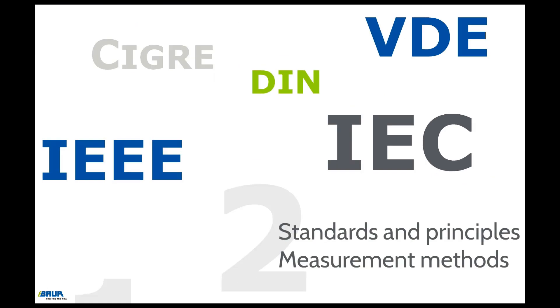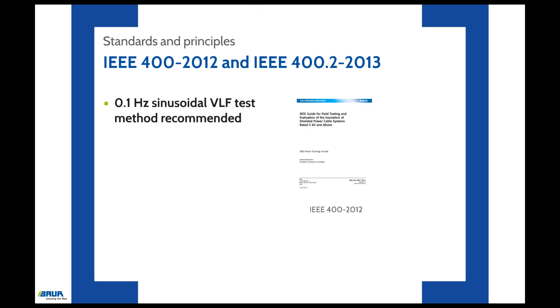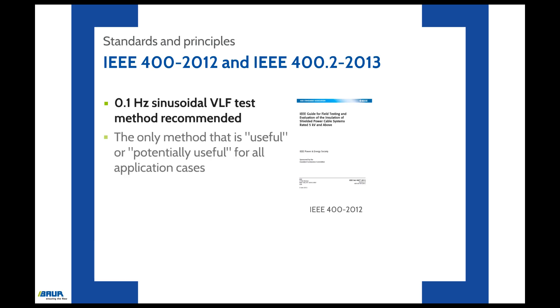Following the introduction of IEEE 400, 2012, the VLF very low frequency test method with a sinusoidal 0.1 Hz is now also listed in the standard. This is the only method listed for which sufficient experience exists on the market and that is classified as useful or potentially useful for all application cases.